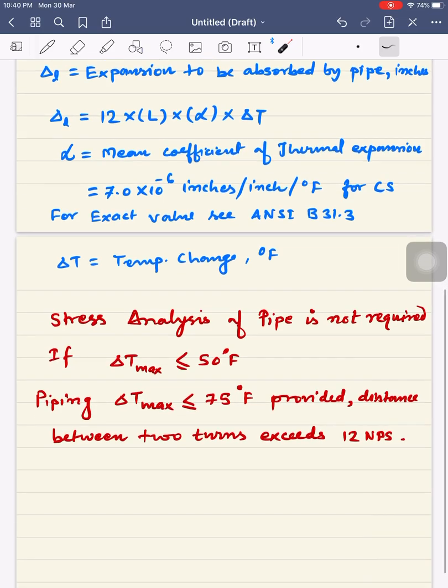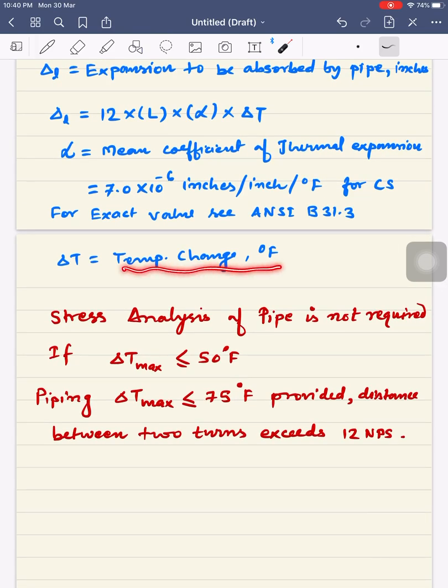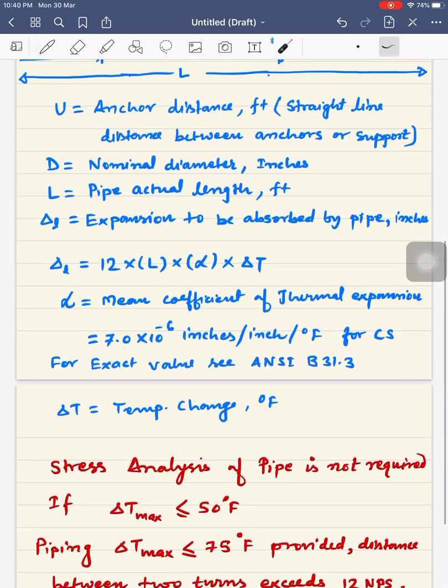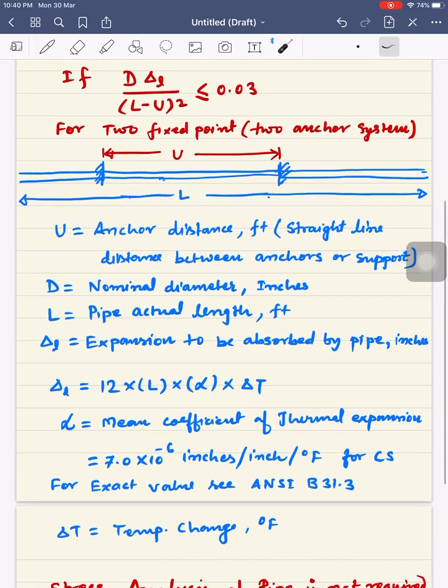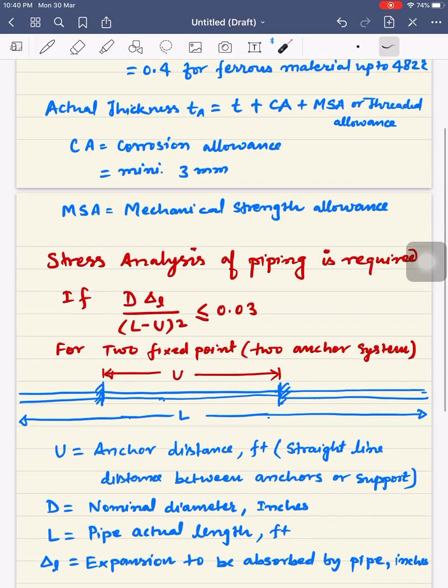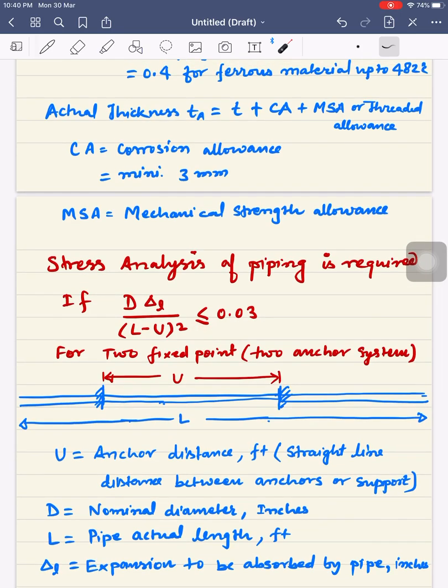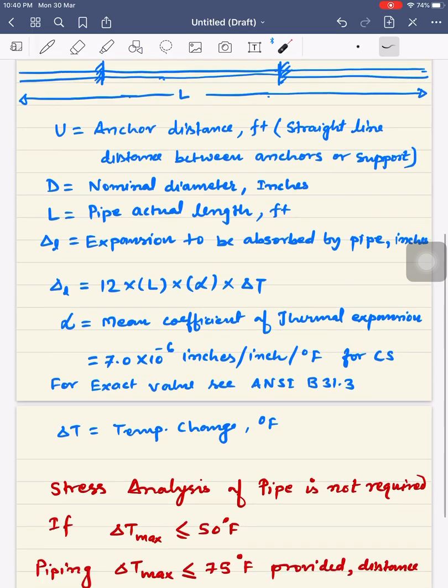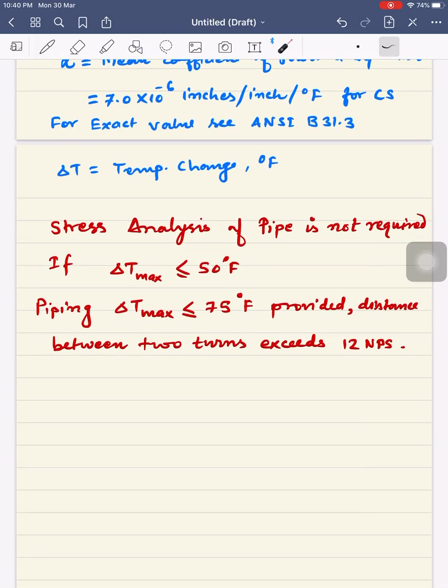Delta T is temperature change in degrees Fahrenheit for this formula. If you put all these values in this formula and it is coming less than 0.03, then stress analysis of the pipe section is required. If not, then not required.